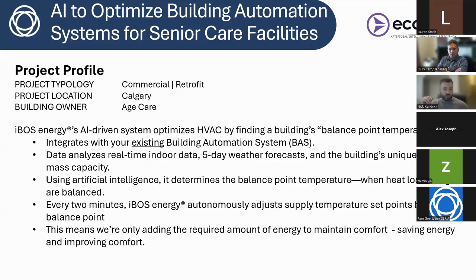And what we do is we just send temperature set point offsets to that BAS. So we're not taking over all those other systems. All we're doing is sending a new set point. I'll show you what that looks like in a graphic in a minute. But instead of, say, maybe 60-degree boiler water going into the loop, we've done our analysis every 2 minutes, and we say instead of that 60, we only need 55. So we bump that down a little bit. We're still keeping an eye on comfort in the building and making sure people are comfortable while saving energy. Because as you can imagine, if you don't raise that temperature as high, you're going to save more energy on that boiler loop, because you're not using as much natural gas to get to that set point.